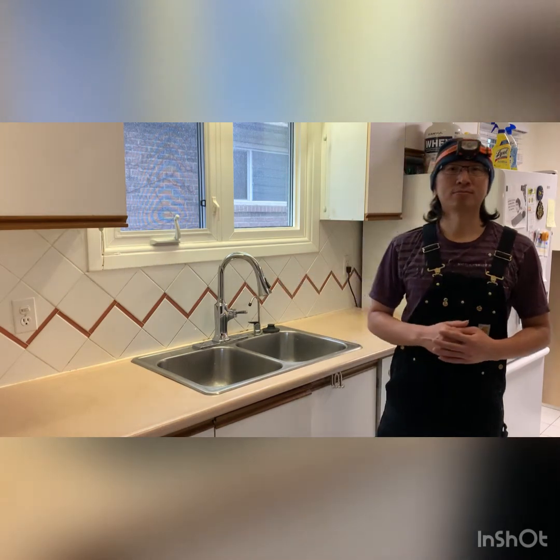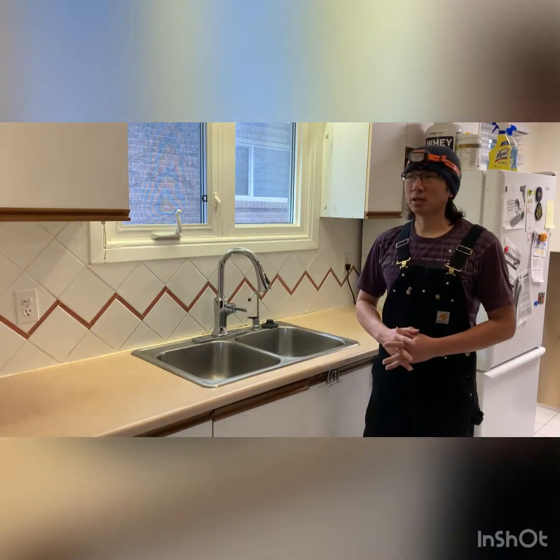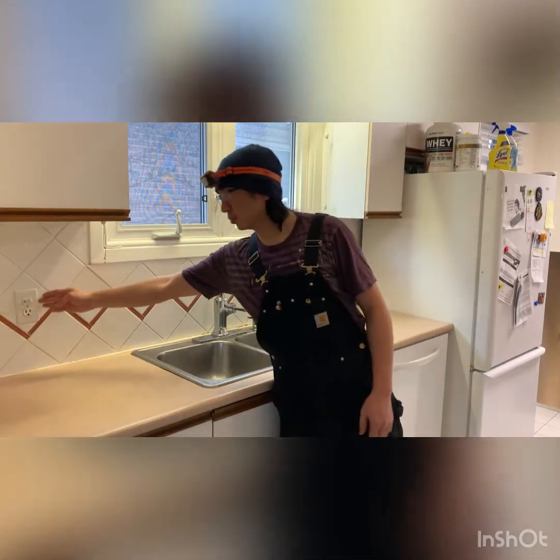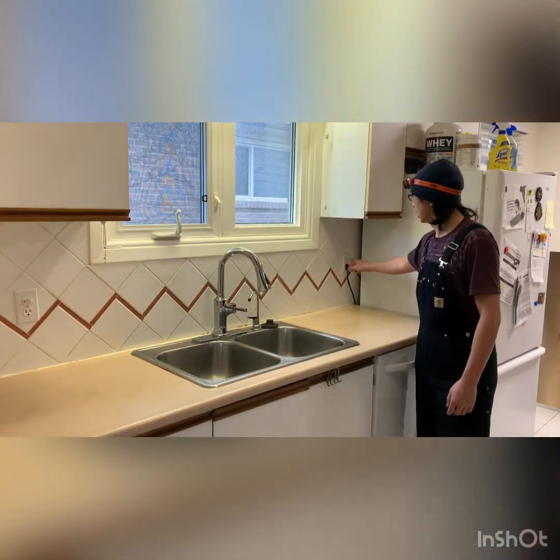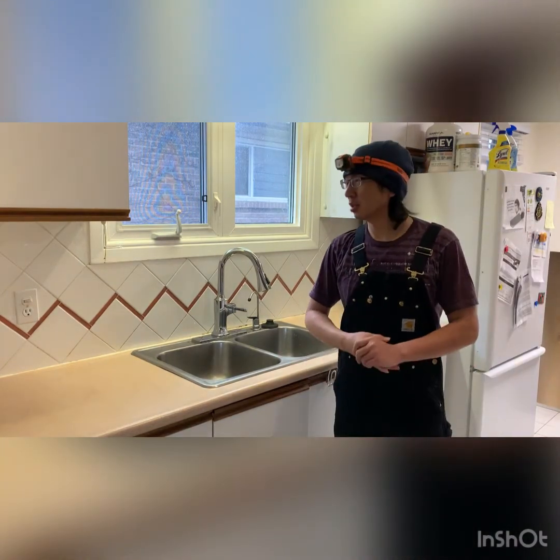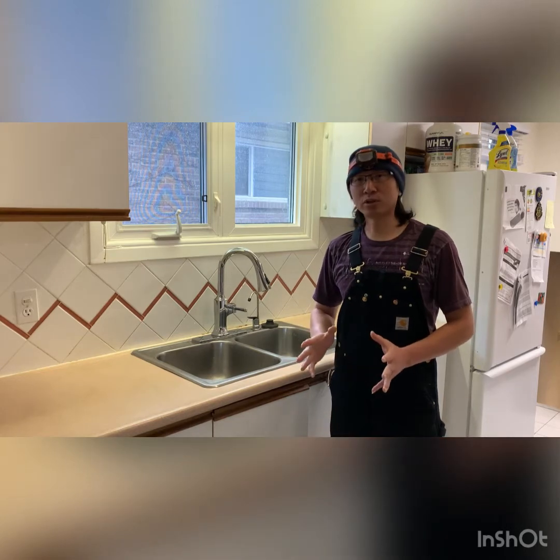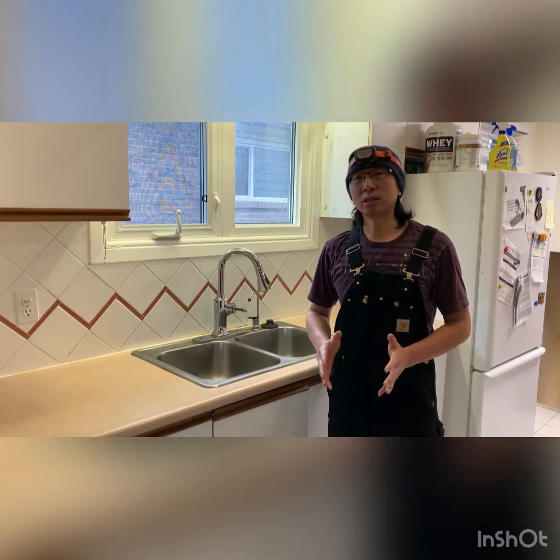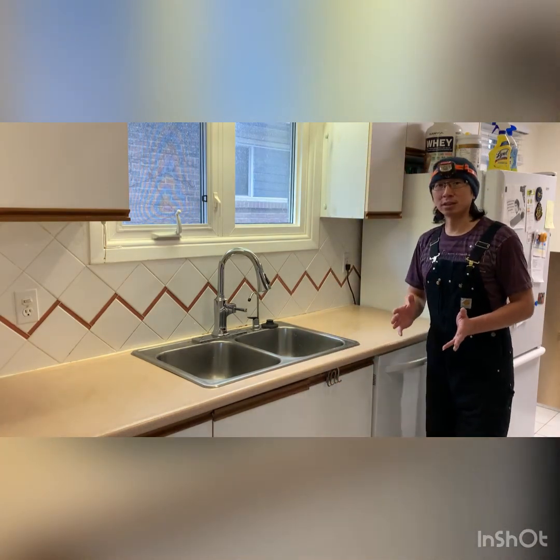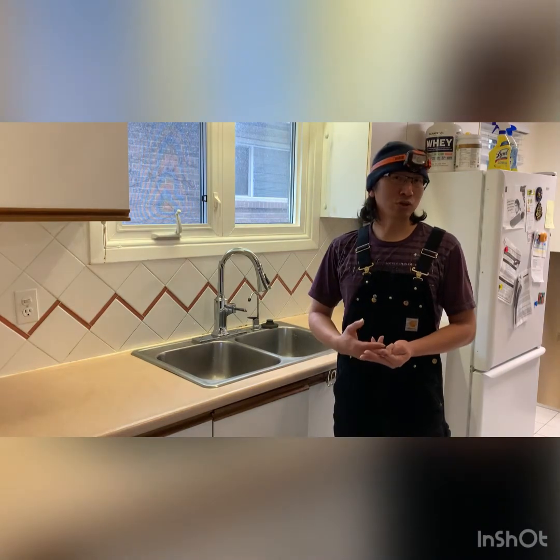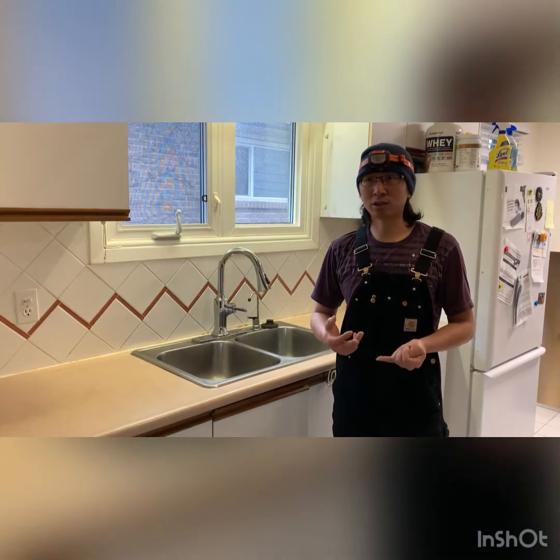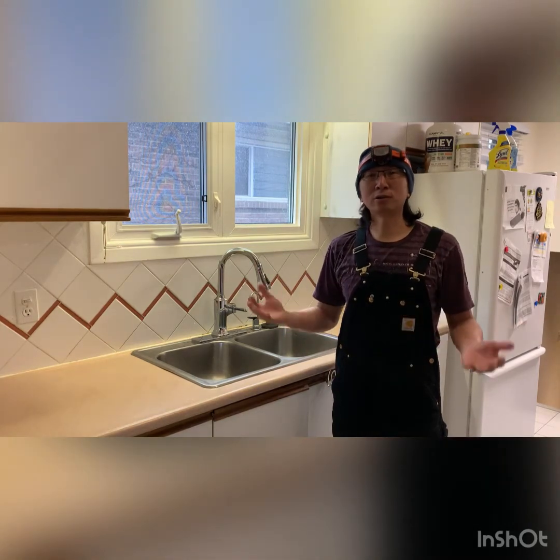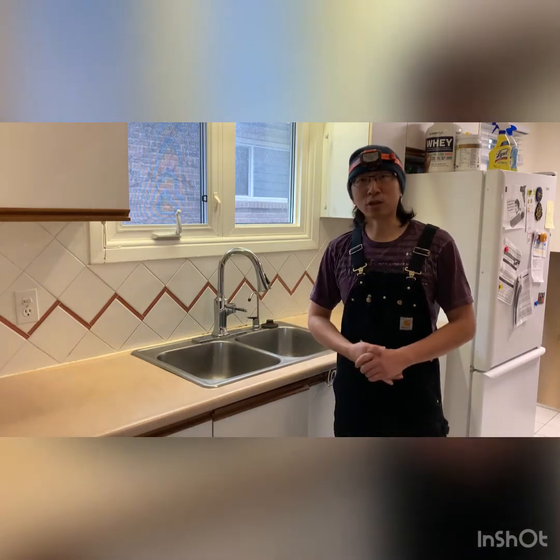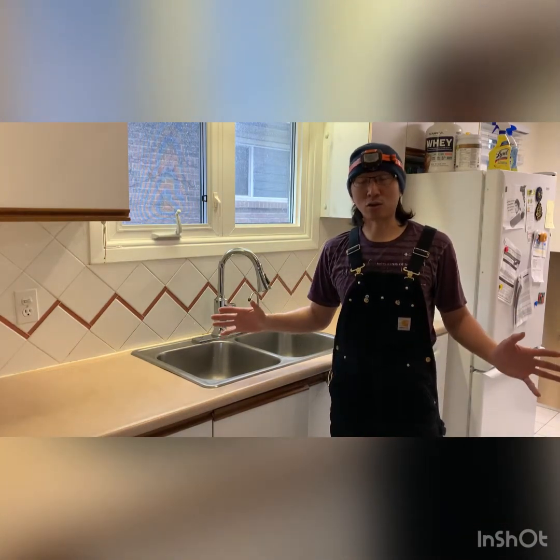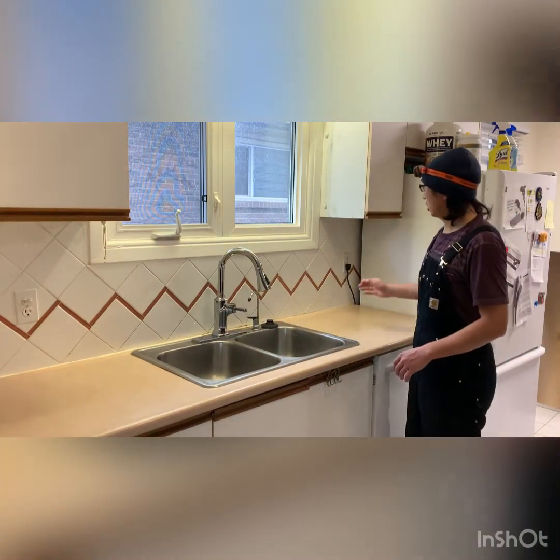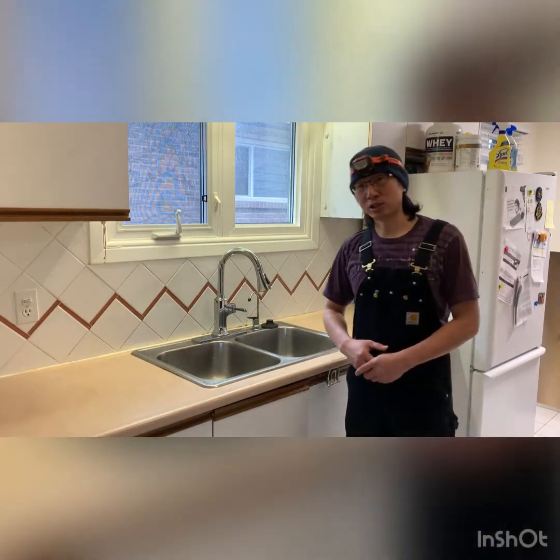Today I'm going to show you how to get a GFCI function to your old kitchen split receptacle circuits. So what is a split receptacle and why do they install split receptacles for the kitchen countertop? There is a reason: the split receptacle will provide more power for the kitchen. Especially the kitchen, you have a coffee machine, a bread toaster, an air fryer, a hot water maker, and now you have hundreds of appliances you want to plug in when you're cooking, and you want it to be fast too. That's why you need lots of power, and that's the design reason for the split receptacle.